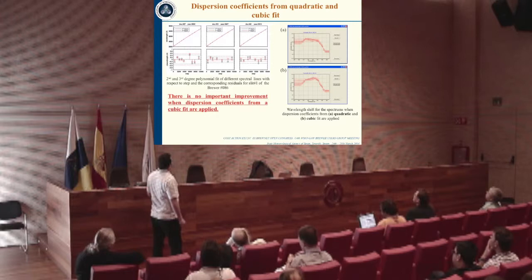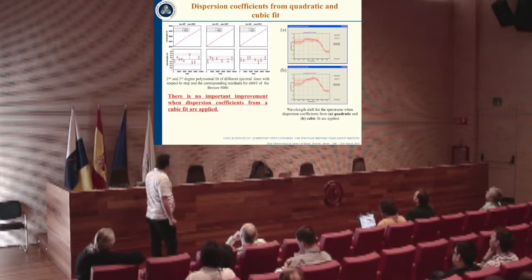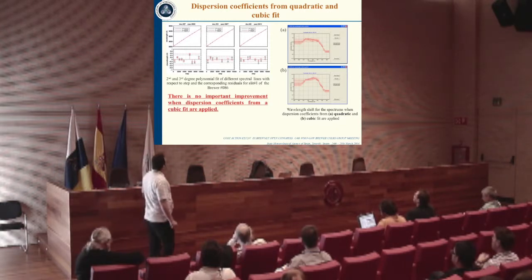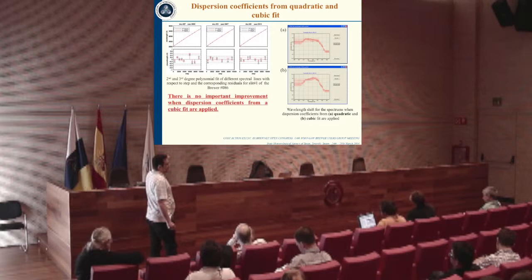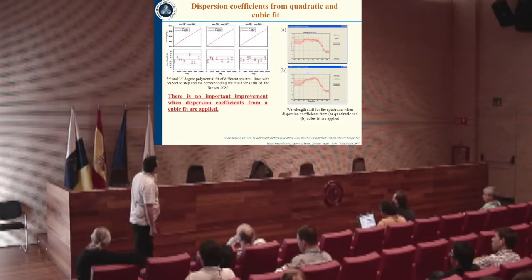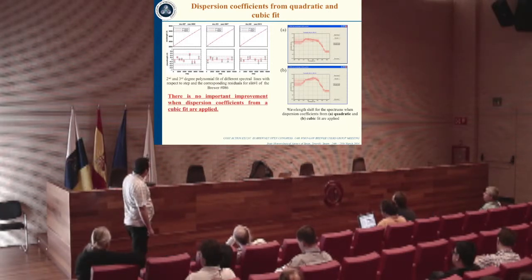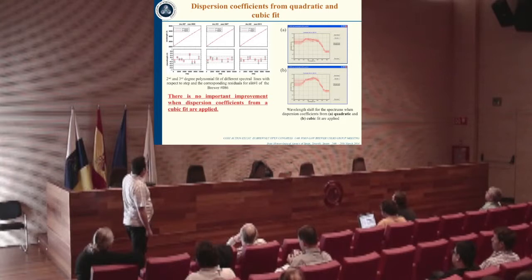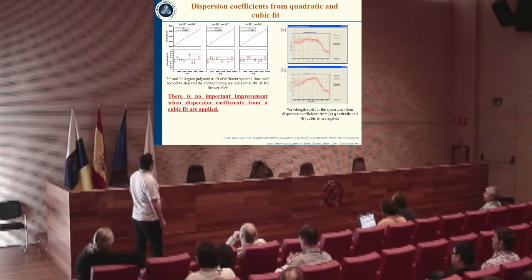The results are for slit 1 of the double monochromator Brewer number 86. In the lower graphs, you can see the corresponding residuals for each case. As we can see here, the residuals are generally lower when the third order polynomial fit is used.